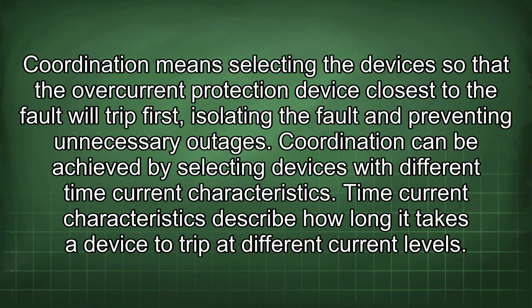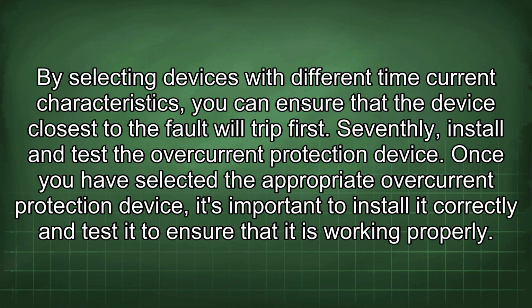Coordination can be achieved by selecting devices with different time current characteristics. Time current characteristics describe how long it takes a device to trip at different current levels. By selecting devices with different time current characteristics, you can ensure that the device closest to the fault will trip first. Seventhly, install and test the overcurrent protection device. Once you have selected the appropriate overcurrent protection device, it's important to install it correctly and test it to ensure that it is working properly.